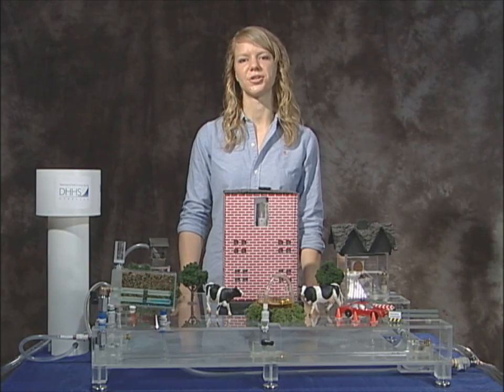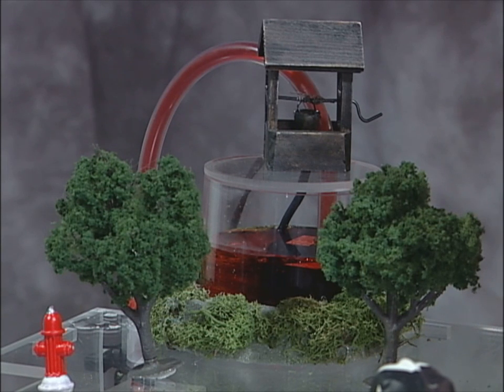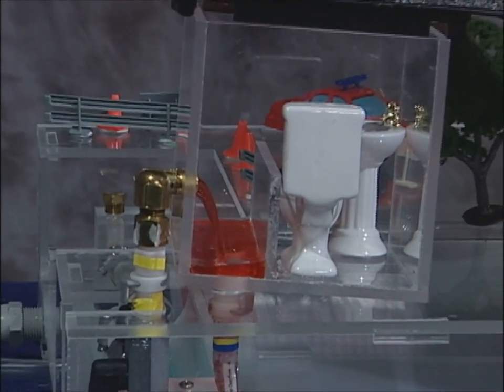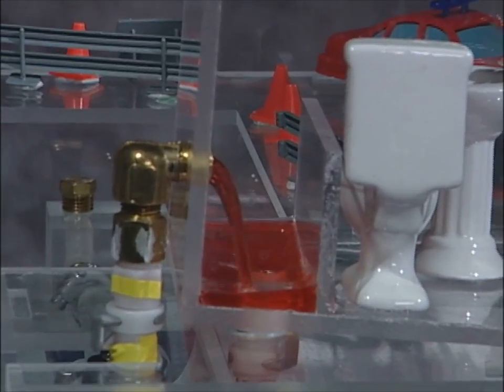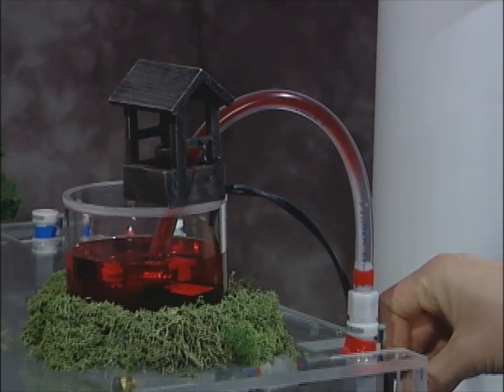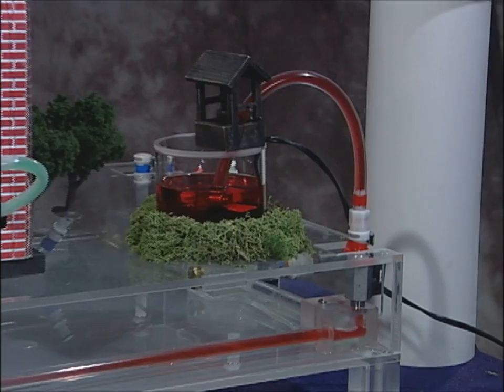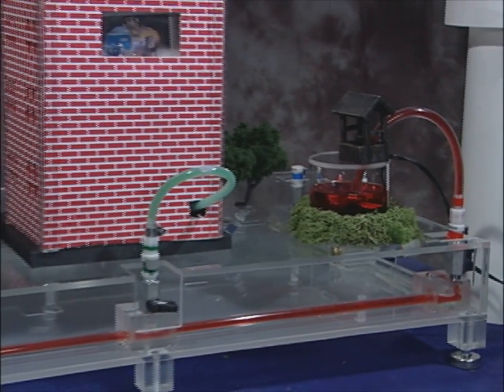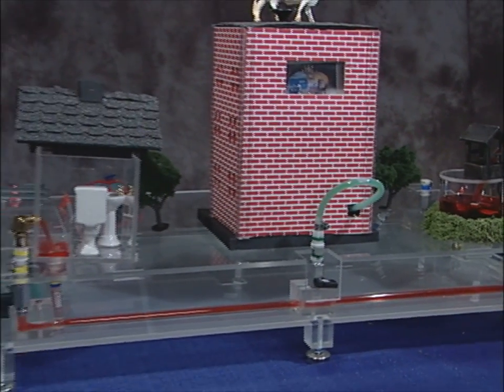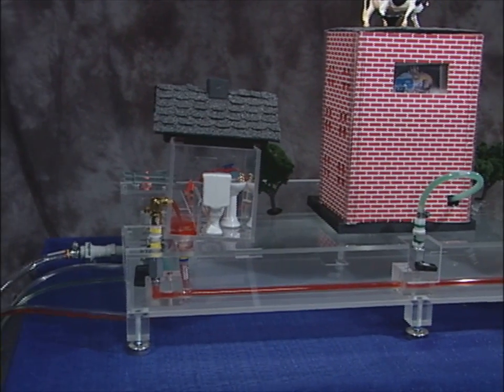First, let's look at a back pressure scenario. The first back pressure scenario is created where a private water well is connected to the public water supply. In some cases, residents may not realize that a private well, which produces untreated water, say used for lawn irrigation, is even connected to the distribution system through plumbing in a home or business. This is a route that bacterial or chemical contamination, such as nitrate, may enter the system.